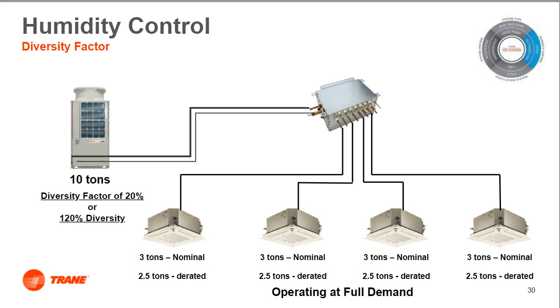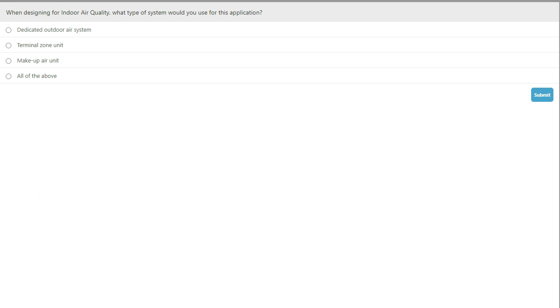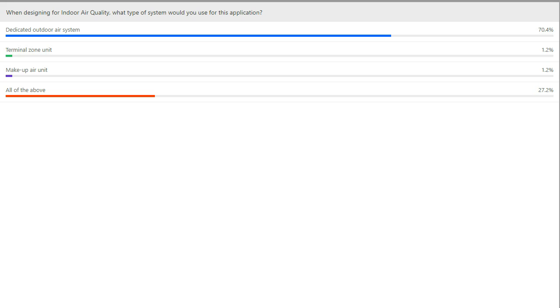And at this time, we'll go ahead and take another second for another quick poll. When designing for indoor air quality, what type of system would you use for this application? Would it be a dedicated outdoor air system? Would you use the terminal zone units or a makeup air unit? Or all of the above? Another second, and let's check our results. Excellent. So a lot of you chose to use the DOAS system as your main point of indoor air quality. And there are also other applications that involve the terminal zone units and the makeup air unit.